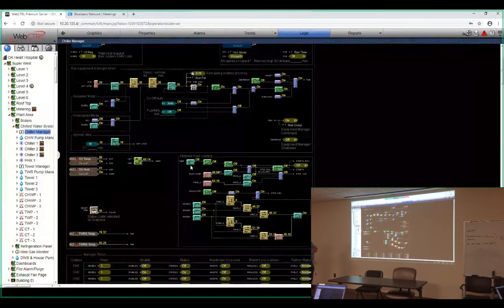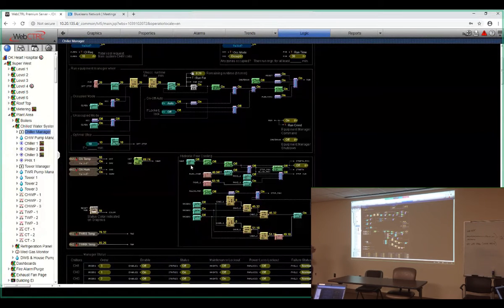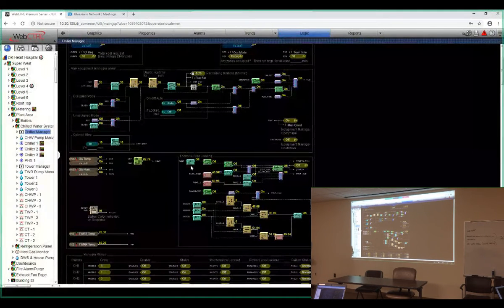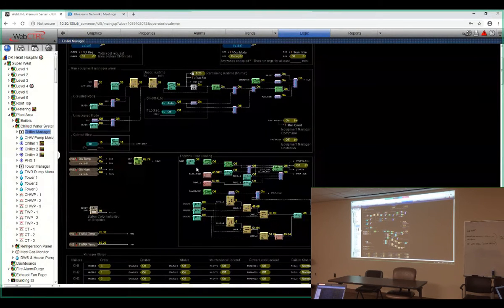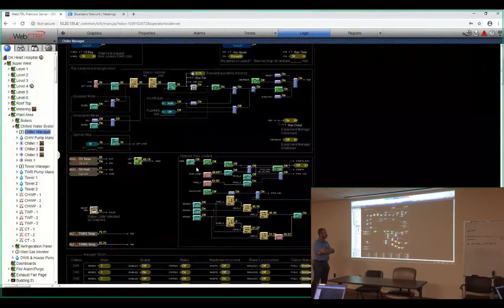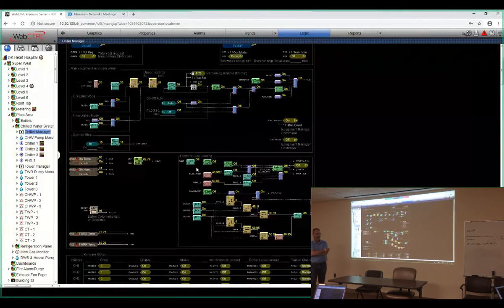Sorry, when the outdoor temperature gets below 33 degrees for 20 minutes, we're going to transition into that cooling charging mode. We're going to reset the tower temperatures down to 42 degrees. We're going to continue to run the chiller as that temperature comes down. Once the tower supplied temperature gets below 49 degrees, then I'm going to open the valves on the free cooling heat exchanger and send a stop command to the chiller.